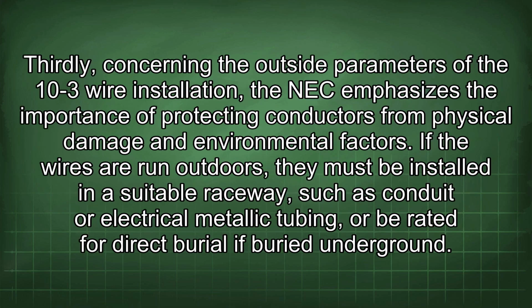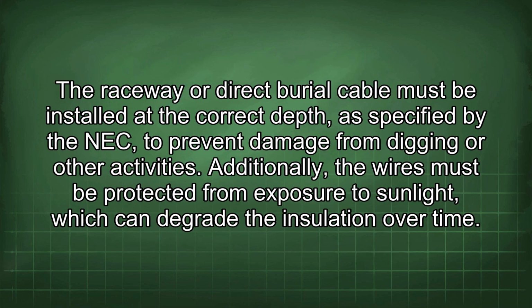Thirdly, concerning the outside parameters of the 10-3 wire installation, the NEC emphasizes the importance of protecting conductors from physical damage and environmental factors. If the wires are run outdoors, they must be installed in a suitable raceway, such as conduit or electrical metallic tubing, or be rated for direct burial if buried underground. The raceway or direct burial cable must be installed at the correct depth, as specified by the NEC, to prevent damage from digging or other activities.